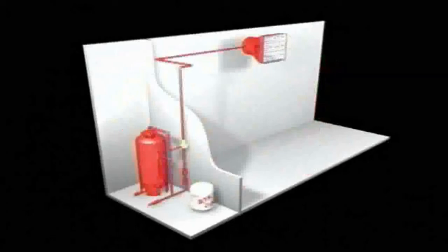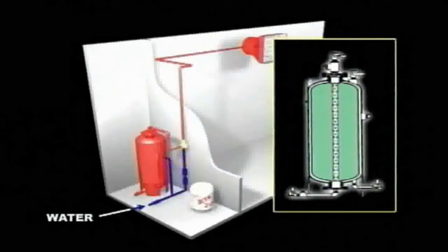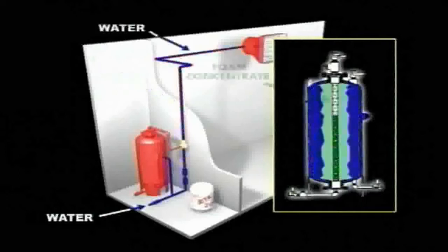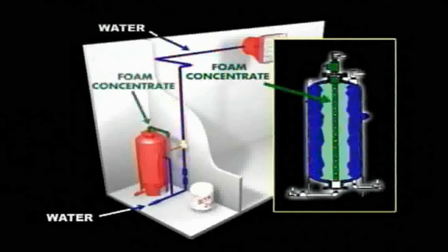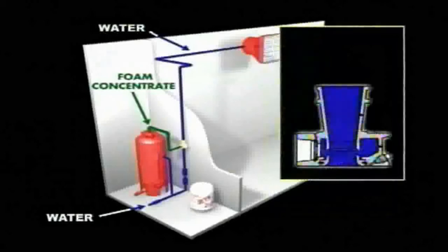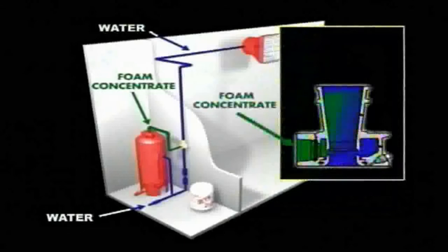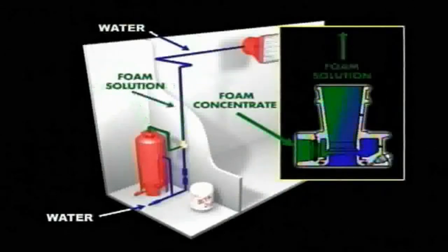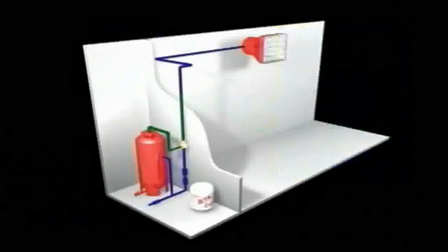The basic system operates solely on water pressure. Water enters the tank inlet, where it surrounds the internal bladder. The pressure forces the Jet-X foam concentrate through perforated tubes to the tank outlet, where it's routed to the proportioner. Simultaneously, water is directed to the proportioner at the same pressure as the foam concentrate. The Venturi effect of the proportioner mixes the foam concentrate and water, creating a 2.75% foam solution, or 2.75 gallons of concentrate to 97.25 gallons of water.